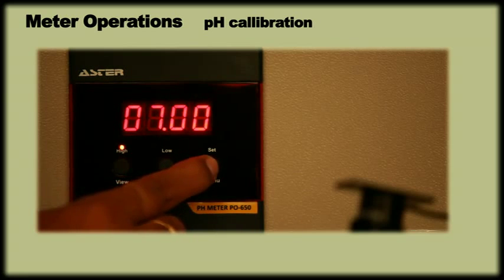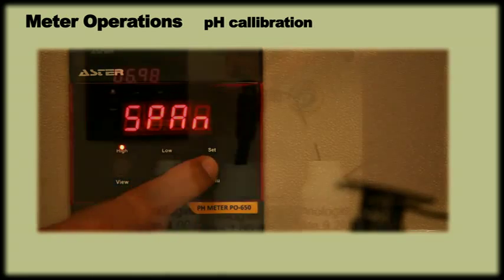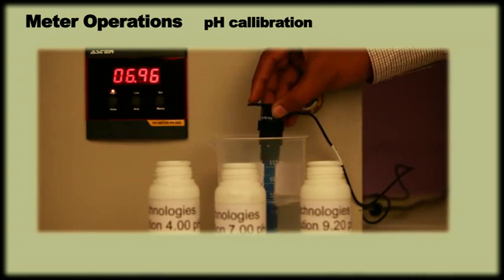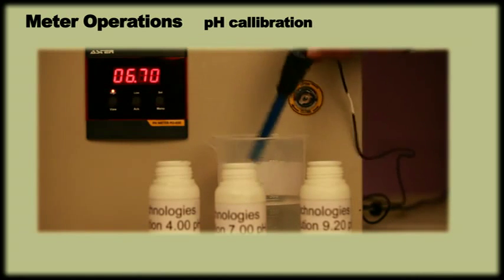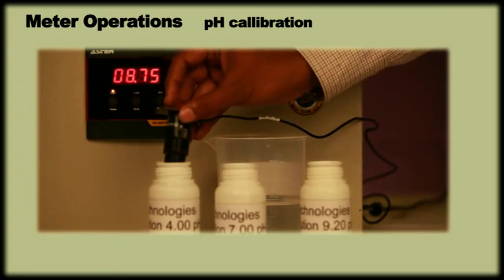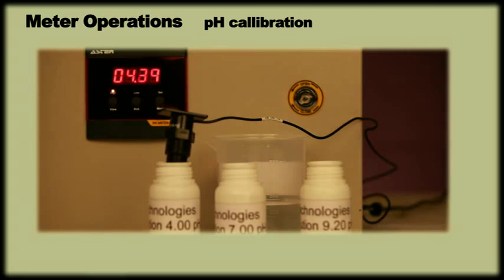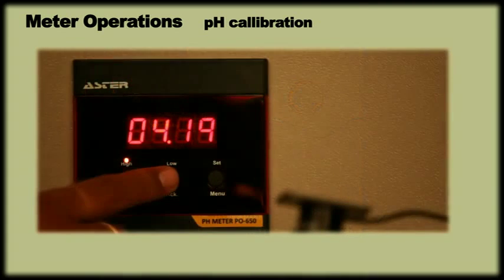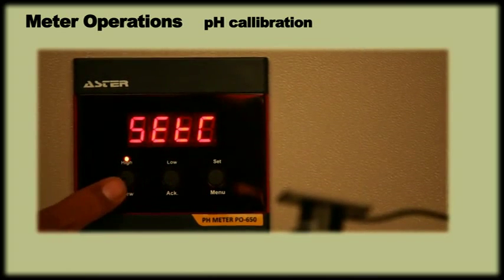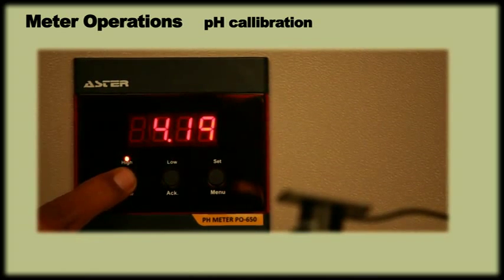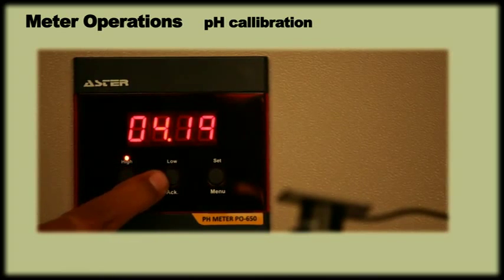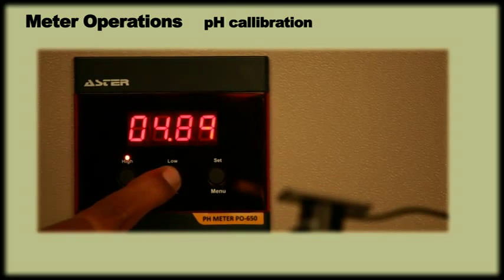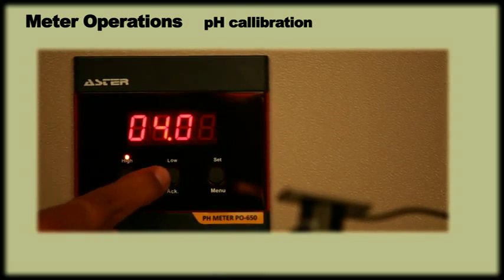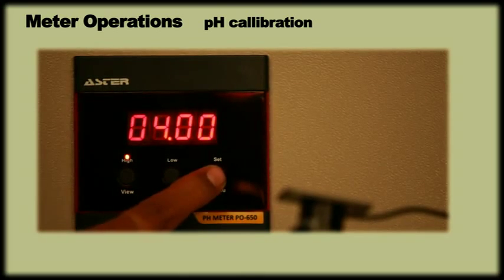Next, the display will show span. Press menu key again. Now, rinse the sensor with water and dip the sensor either in 4 pH or 9.2 pH solution and wait till the reading stabilizes. Press ACK key to select SETC and set the span value. Then display will show a reading with its first digit blinking. Set this value to 4.00 or 9.2 depending on the solution using View and ACK keys and press menu twice to end the calibration.